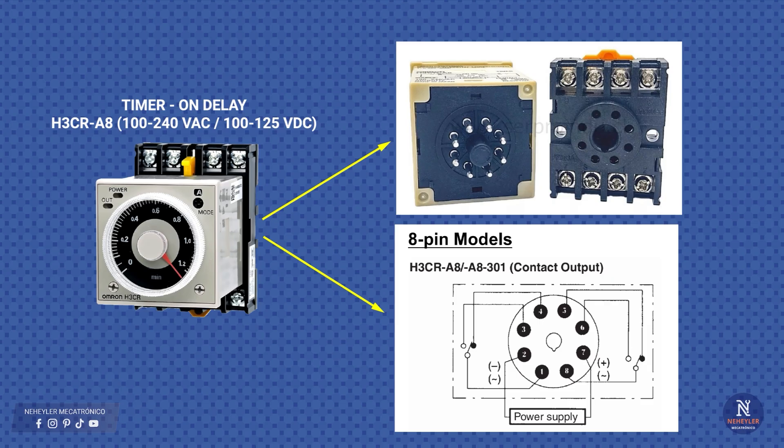For this project we are going to use this timer model, H3CR-A8 on delay. This type of timer needs a special base to be mounted on a DIN rail, which makes installation in electrical panels easier. At the bottom we see the electrical diagram according to the manufacturer's datasheet, where its 8 pins and the function of each one are clearly indicated. It is important to mention that if you decide to use another timer model or brand, you must always check its technical data and connection diagram, since the pin and contact arrangement may vary.